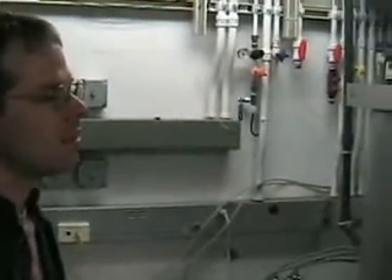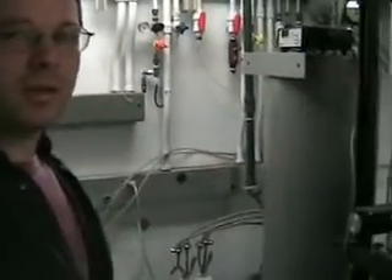Later we can still use a leak detector to pump out this exchange gas when we are at 4K. I was using the same amount just because it's another thermometer as to what's going on in the system. As we transfer helium and it gets really cold — I can check the log — but somewhere at about 40 millitorr is when I start to pump out. The issue is that your main thermometer here is the sorb thermometer, which is what we're going to be watching, but we need to keep the sorb above 20 Kelvin because it's a bit warm so it doesn't start pumping. At about that temperature — about 20 Kelvin — I lose my thermometer here, but I still have an effective thermometer from the exchange gas pressure, which is useful.